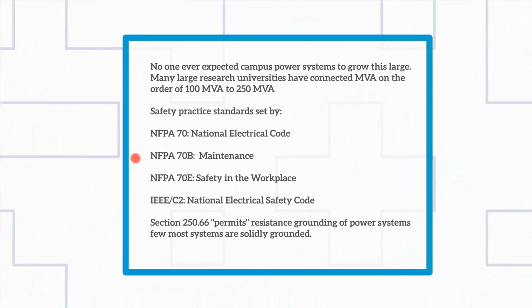Just so you know, listeners, Dave and I did manage to get some code changes in the appendix of 70E and 70B. As we said, this goes back, don't you remember that? We could not get it in the core enforceable text, so to say, but it was a recommendation, and we did manage to point out the different scale of resistance grounding, the amount of fault current you let through for the different types: high, low, and resistance grounded. I've forgotten the kind of code changes we've been able to make, but we have been approaching this.